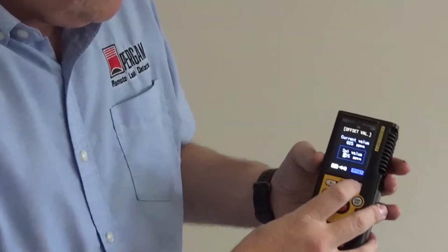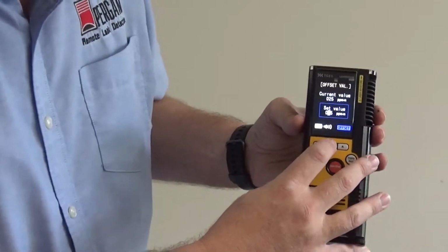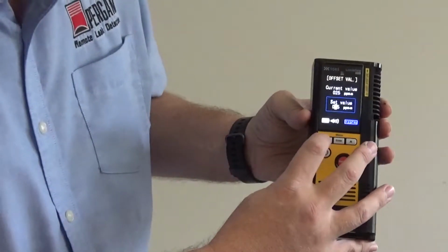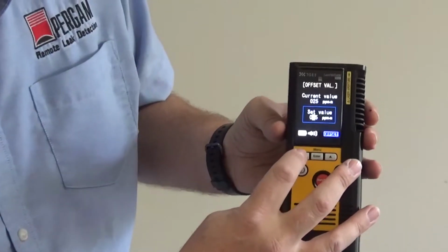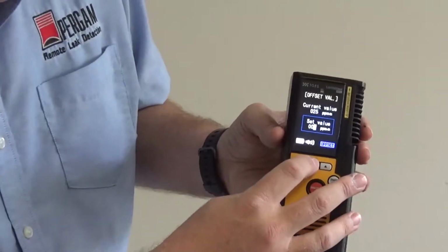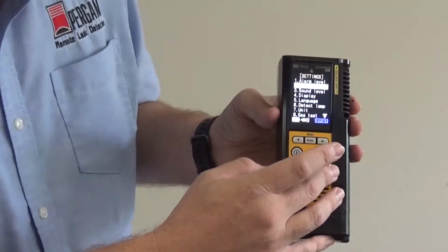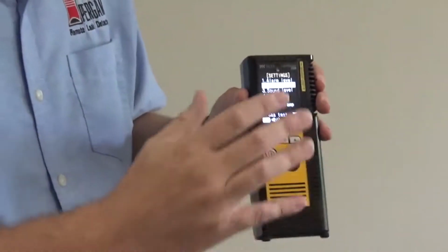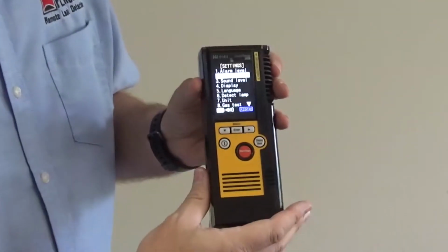So in this case, it's set at 25, and so we're going to hit enter, and we're going to change this setting to just 5. So I'm going to scroll down. We're at 15. Now we're at 5. 0, 0, 5. We're going to hit enter. And we'll save this information in the menu structure here. And once again, this will not change unless somebody else goes in after me and physically changes this.